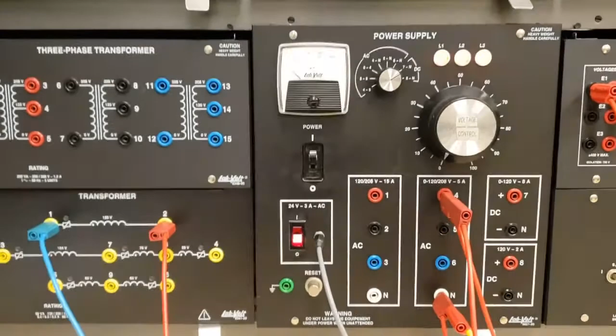Now that we're done with the open circuit test, the short circuit test is just kind of the opposite. Again, we choose a side to apply - this time we apply current to one side and short the other side. Because we're applying current, we want to choose the side with less current needed. A sensible choice is the high voltage side, because the high voltage side of a transformer has the lower rated current. So we choose the high voltage side. If you chose the low voltage side for the open circuit test, the other side is the high voltage side - that's where you apply the short circuit test.